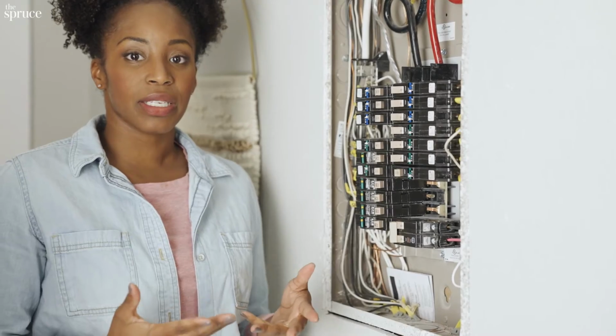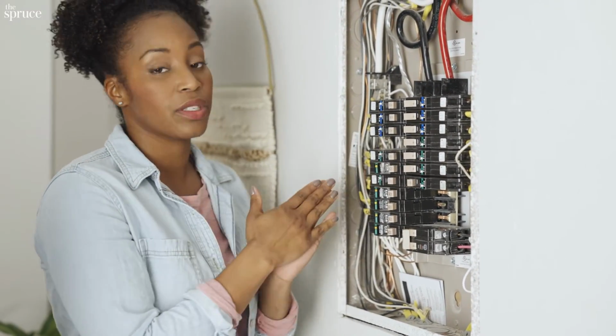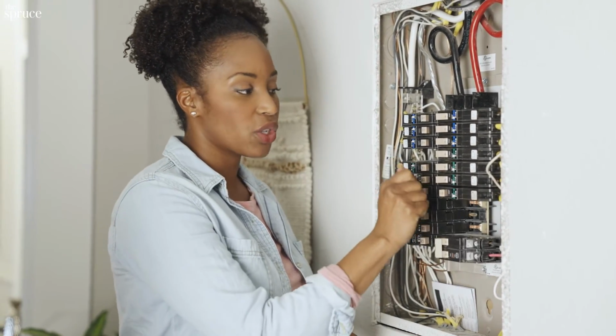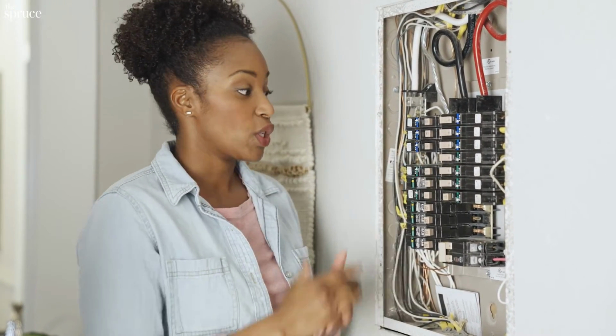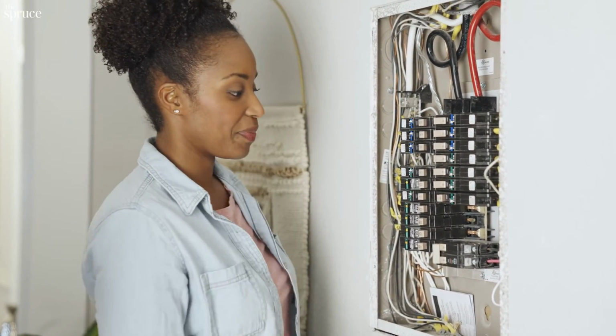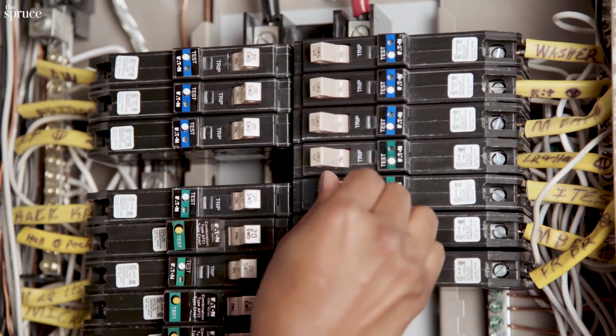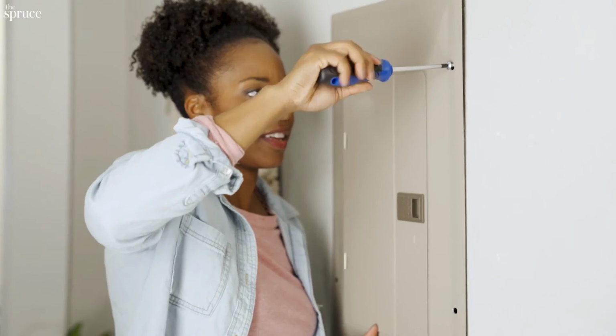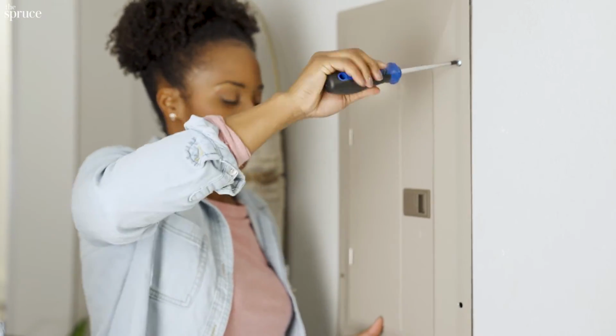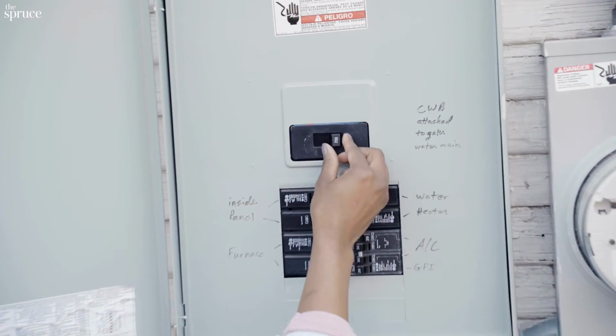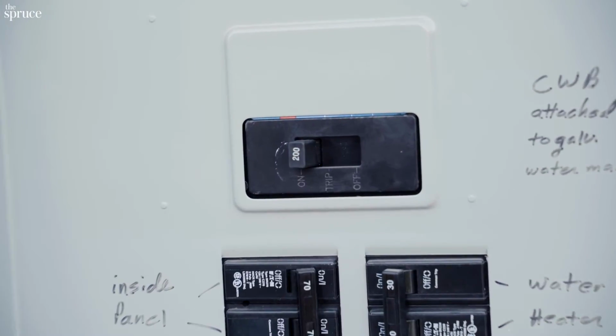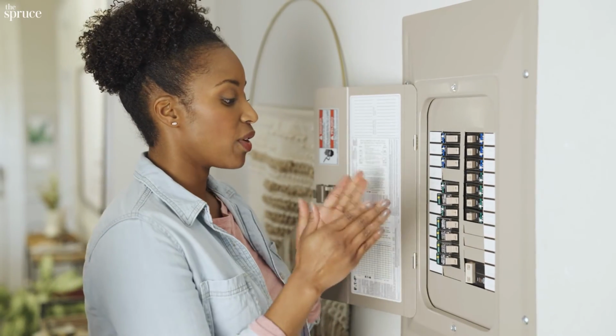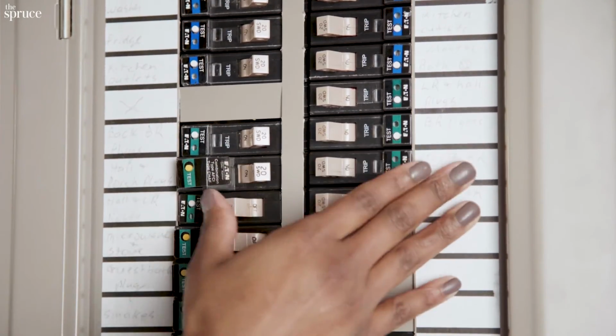And it's a good practice to go ahead and turn all of these circuit breakers off, then turn on the main breaker, and one by one turn each circuit back on. So I'll be putting all of these in the off position now. Now I can screw the cover back over the panel and go outside and turn the main breaker back on. Okay, my main breaker's back on, so I can turn each one of these circuits back on one by one. Let's close the panel door before calling this job done.